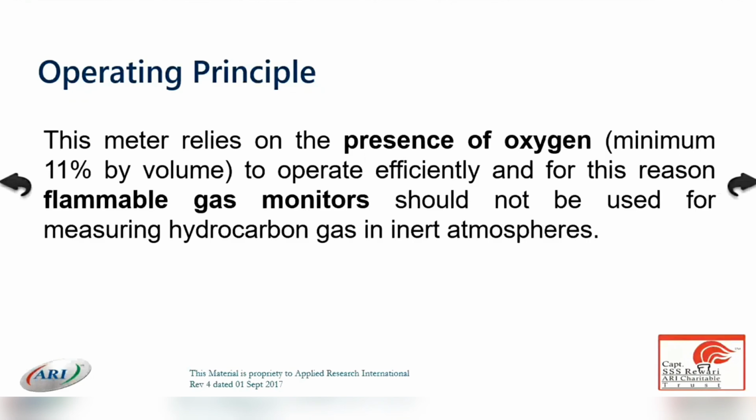This meter relies on the presence of oxygen. As I said, the minimum oxygen required for the explosimeter is 11% by volume to operate efficiently, and for this reason the flammable gas monitors should not be used for measuring the hydrocarbon gas in an inerted atmosphere. It should be in a gas-free state. It can be more than that, but the minimum required is 11% of oxygen by volume.